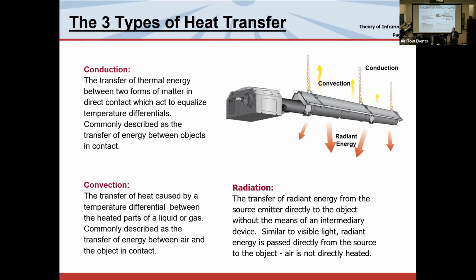Back to my original slide. How efficient are your heaters? We're going to keep coming back to this theme because in a perfect world, an infrared heater would have 0 conduction, 0 convection, and 100% radiant. Right? That would be the perfect radiant heater. It doesn't exist. As a matter of fact, the most our standards recognize in the current standards for testing radiant output is 70%. The other 30% is mixed over convection and conduction. All right. So let's remember that. Touching that stove: hot because I touched it, hot because I kept my hand above it, and hot because I kept it off to the side. And we, as the manufacturer of infrared, want to try and emphasize radiant heat. All right, next slide, please.